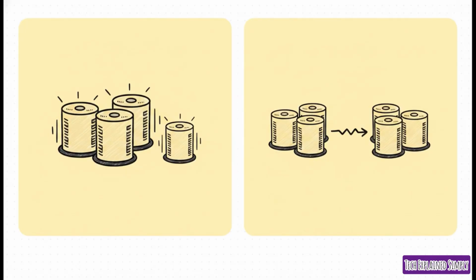Facility engineers measure this backup capability in tiers. If your baseline requirement is N, an N+1 design means you have exactly the components you need to run plus one single backup component, just in case. But for mission-critical facilities, they often go with a 2N design, meaning completely independent, fully mirrored backup systems, literally a clone of the whole setup. If one entire power or cooling path dies, the other side takes over flawlessly.